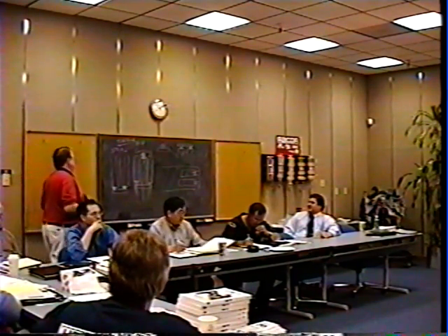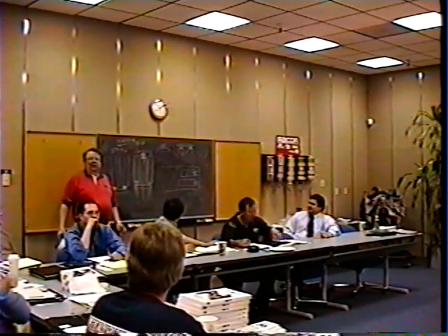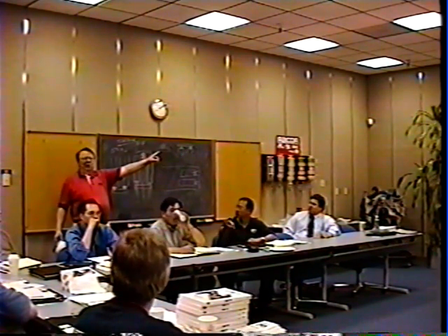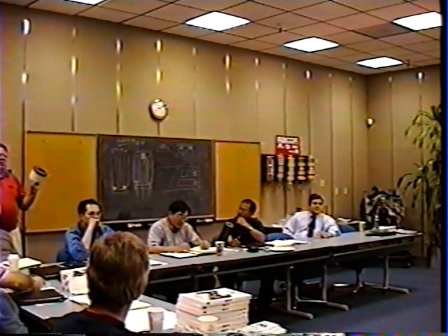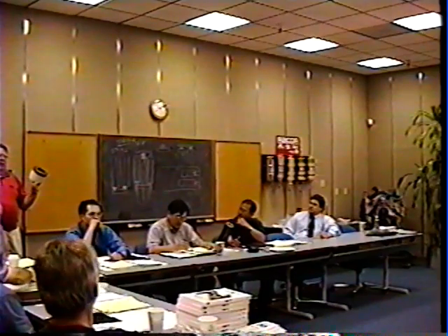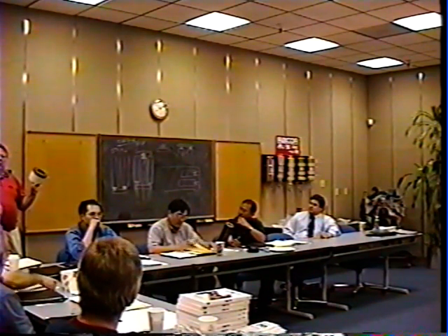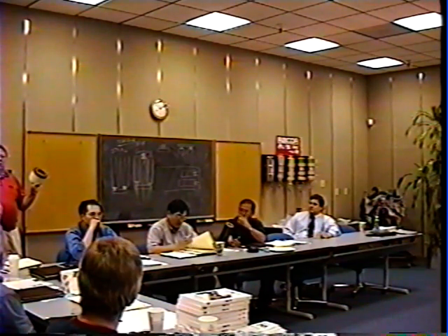Why would it be important to torque and make sure we have a good seal? Because the elements like to be torqued. If you don't get it right, you'll have a leak at the bottom. Remember, 500 gallons a minute is going through this vessel. And by doing that, that allowed us to qualify our element up to 1,000 gallons a minute in actual operation in the field. So now you think about, in a worst case scenario, at 1,000 gallons a minute at 3% water. It's a lot of water.